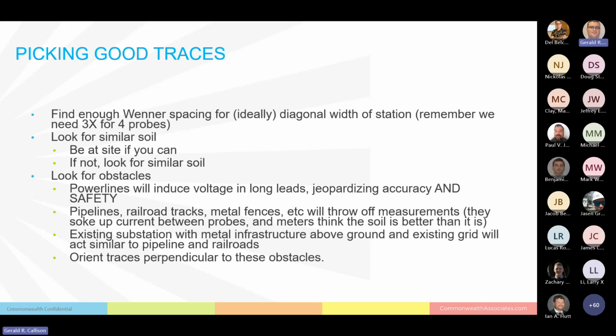Also, things like pipelines, railroad tracks, and metal fences can be a problem. What happens is the meter injects current, and that current gets picked up by the pipeline or railroad tracks, then dropped off at the next probe. The meter won't know there's a pipeline picking up the current, and it will think the soil is better than it actually is.